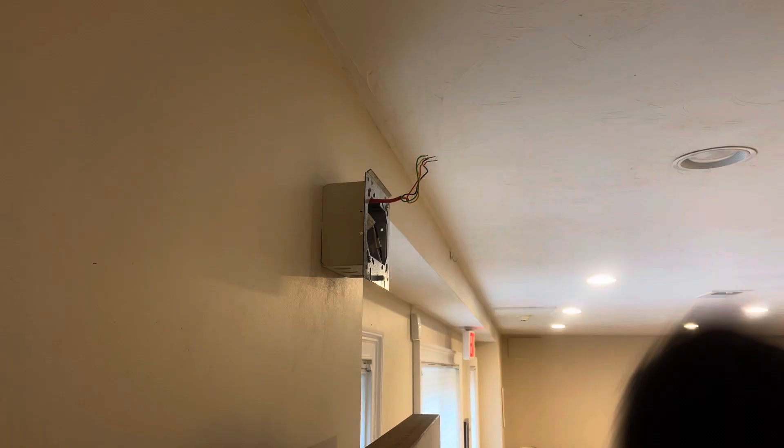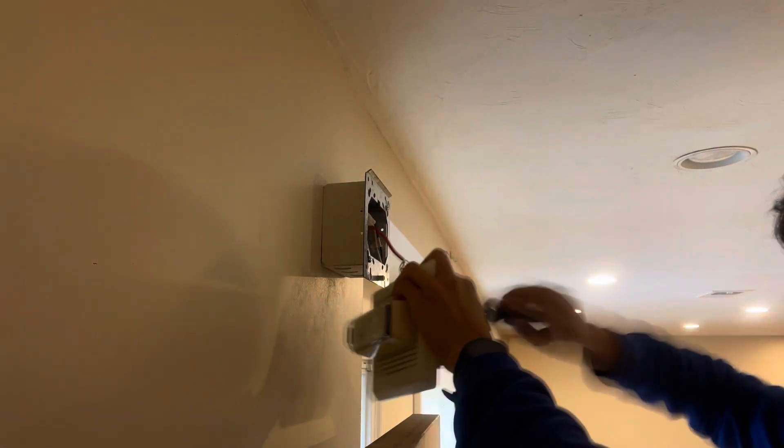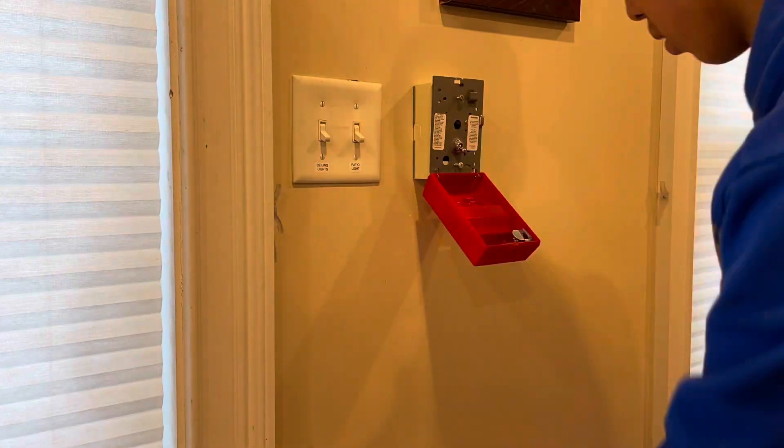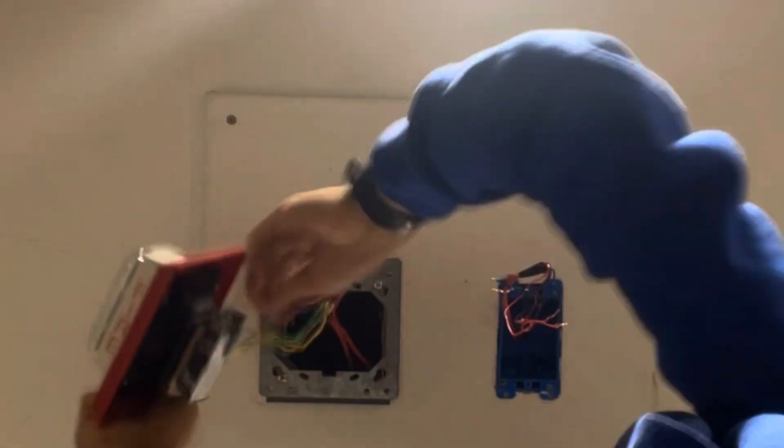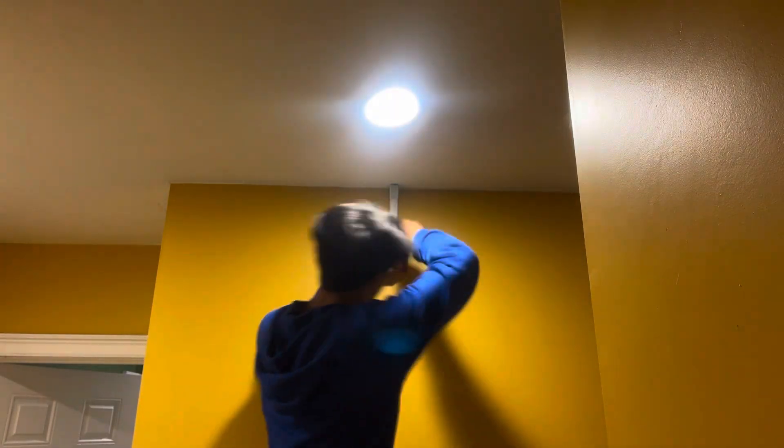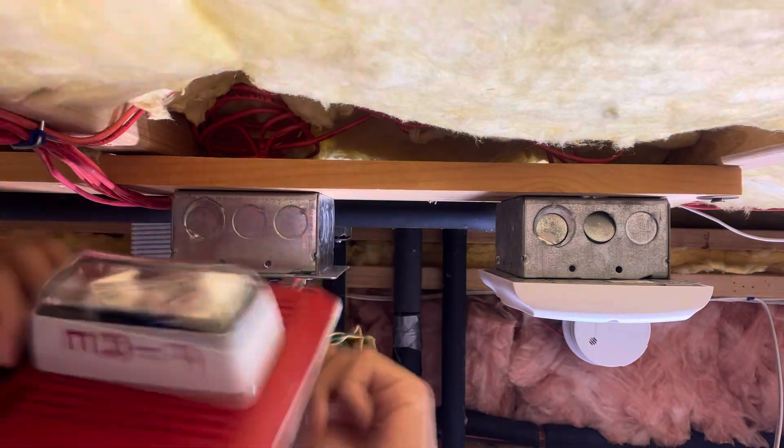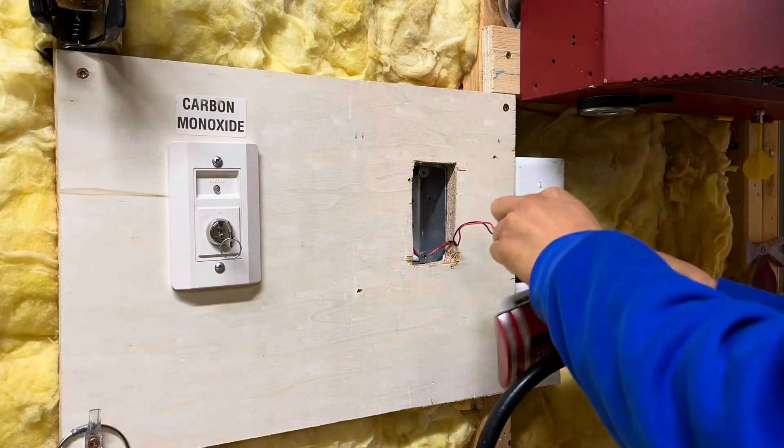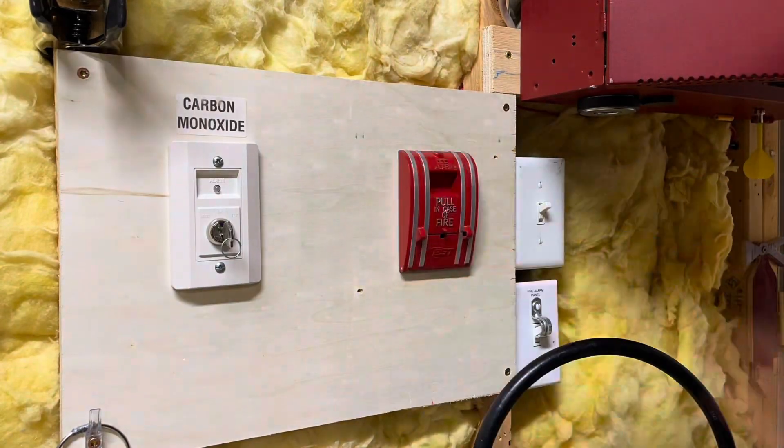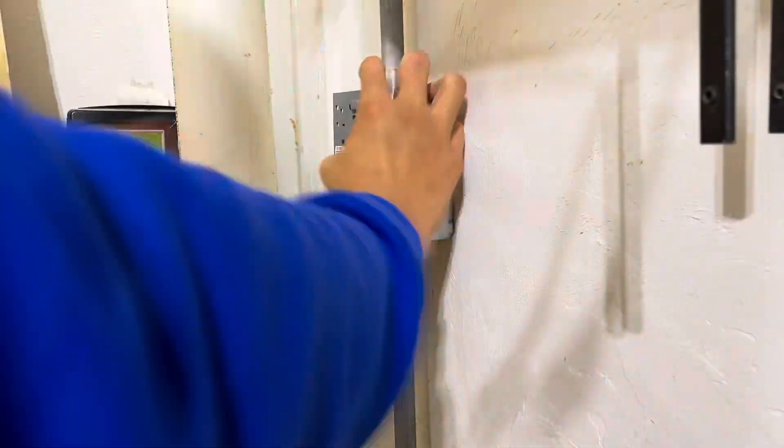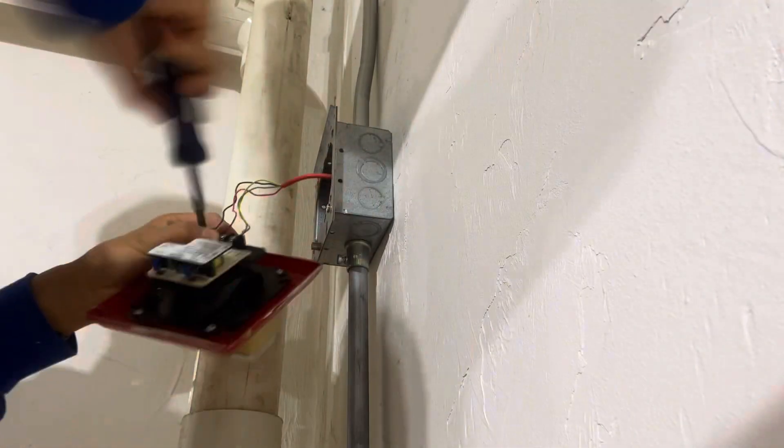As per usual, I've time-lapsed the rest of this process. So I'm installing a white horn strobe on the other side of the basement. Of course it has a white back box to complement it, but it looks a lot nicer when it's white. In this case here, I'm installing another SIGA pull station, this one's single action. Of course here in the fire museum on the ceiling, again another integrity horn strobe. Technically this one's not ceiling mount because it doesn't have the ceiling mount sleeve, but the strobe is the same so it provides the same candela coverage. And it really doesn't matter anyways because it's a demo system. And of course there is a smoke detector next to it that's Edwards. The bathroom here, this right here is actually a 110 candela strobe, so it's really, really bright. But this is unenhanced, of course, and it mounts on a single gang box. Here in the utility room, I'm installing another integrity horn strobe. This one is actually enhanced, so it should sync with the one other enhanced device in the fire museum, but none of the others should sync with it. And then here in the utility room for the pull station, I'm installing a 270 series pull station. This one was originally addressable, but I converted it. Same with this pull station in the garage. It was quite difficult to fit this into the box because of how many wires there were. And then one more unenhanced device. This unit here is in pretty bad condition.